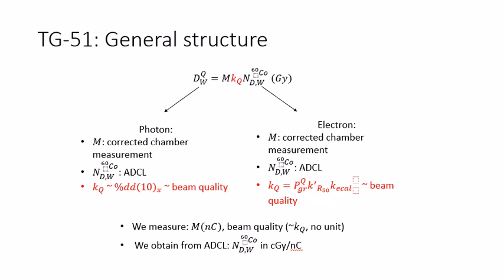Now let's take a look back at TG51 general formalism. We have discussed how to correct for the chamber raw reading, which is the corrected reading M. We know that NDW cobalt-60 is a factor that comes directly from the calibration lab, which we don't need to do any measurement for in the TG51 annual test. So what's left is the KQ factor, the beam quality factor.